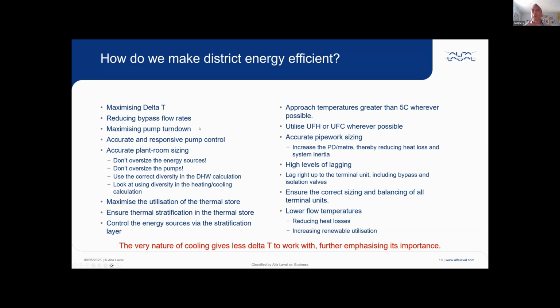Make sure that you've got that big delta, that you have accurate pump control so that it meets the demand, so that the system is reliable. And we absolutely need to stop oversizing the plant rooms, which we do on a regular basis. We overestimate demand. We then oversize the energy sources as well. We use lower diversity than we should do in the calculations. Well, we don't add diversity into the cooling when we should.